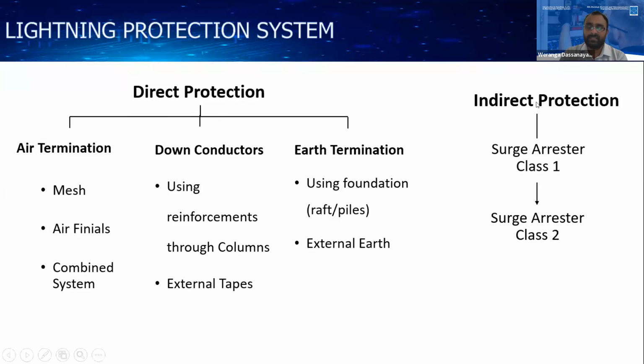And indirect protection means if lightning occurs in a transmission line or distribution line, indirectly it comes to a building or the premises via your power distribution line. So we have to protect the building or the premises from these two types of lightning or switching surges.